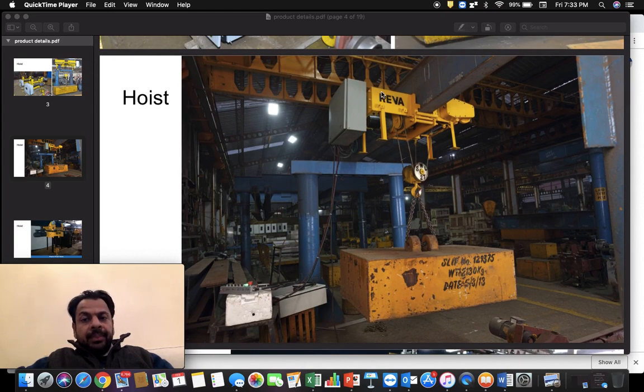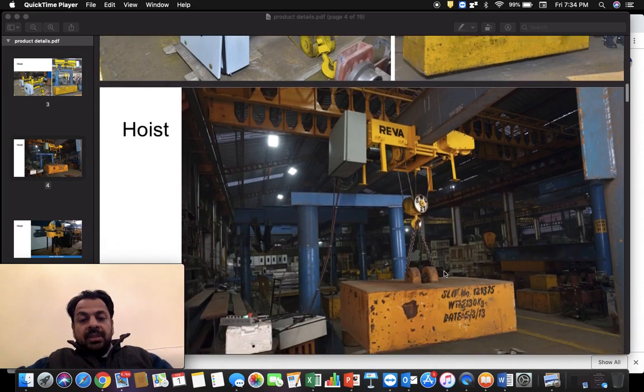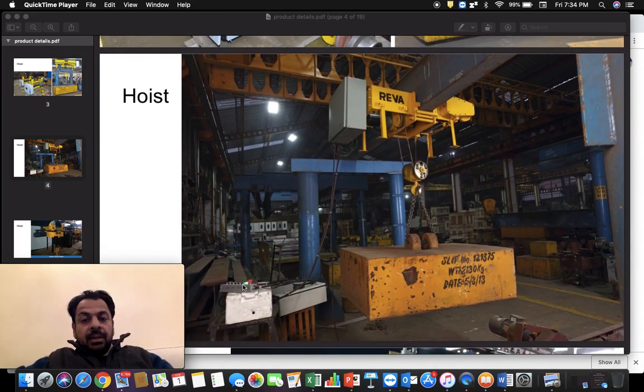To summarize the parts of a hoist: there is a hoisting motor, hoisting gearbox, hoisting drum, wire rope wound on it, equalizing pulleys, bottom block pulleys, bottom block hook arrangement, free end clamp, cross travel gearbox, cross travel motor, cross travel brake, cross travel wheels, up and down limit switches, and cross travel limit switches. The entire hoist is controlled by a control panel — when you press the up button on the pendant, the contactors or VFD drive activate and provide power to the motor and brake simultaneously from this control panel.